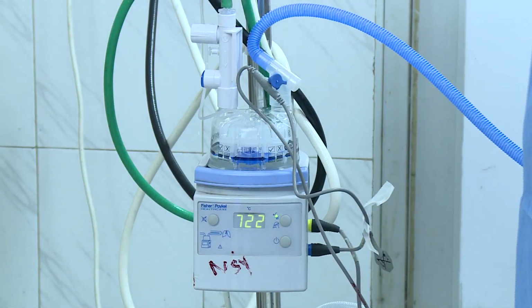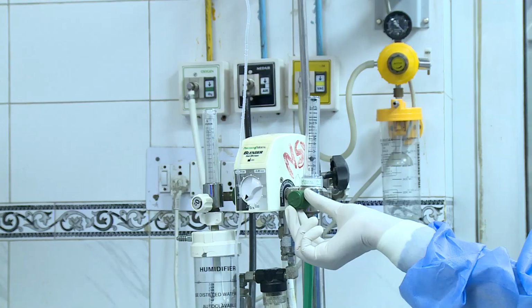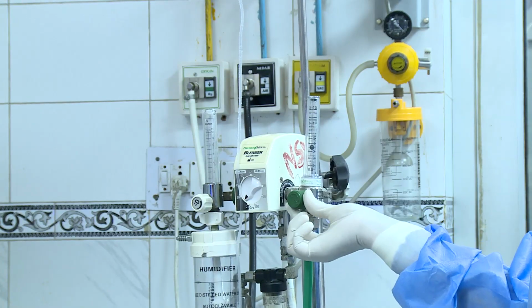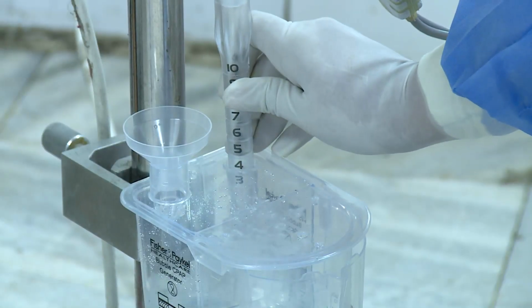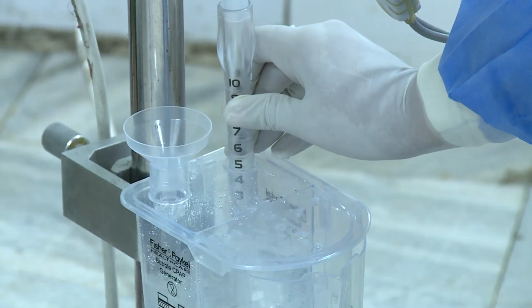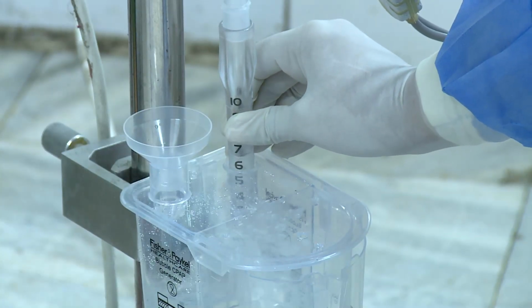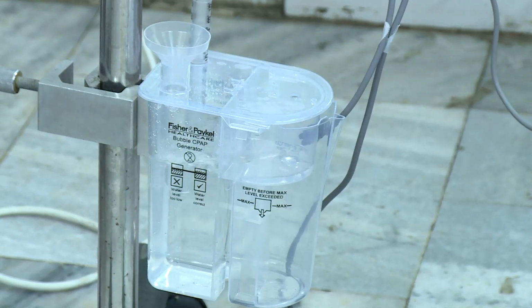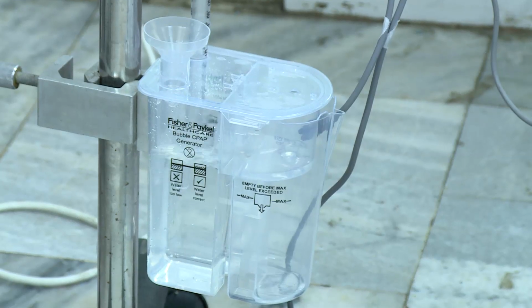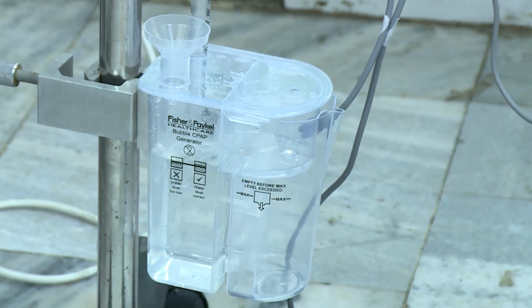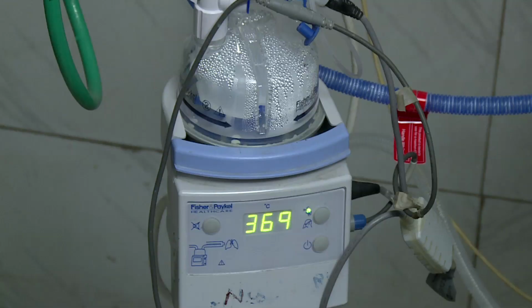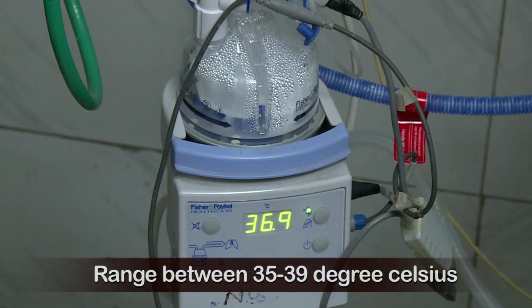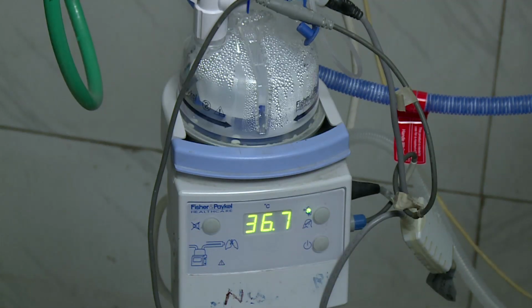Switch on the humidifier. The flow rate is set at 5 liters per minute and the pressure is selected by inserting the graduated expiratory tube in the bubble chamber. Observe if the bubbles are coming out in the bubble chamber, and in case there are no bubbles, look for any leak in the circuit. Wait till the temperature of the humidifier rises to a desired range of 35 to 39 degrees Celsius before connecting the patient to the CPAP.